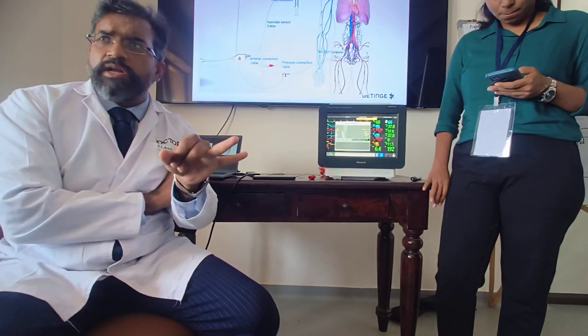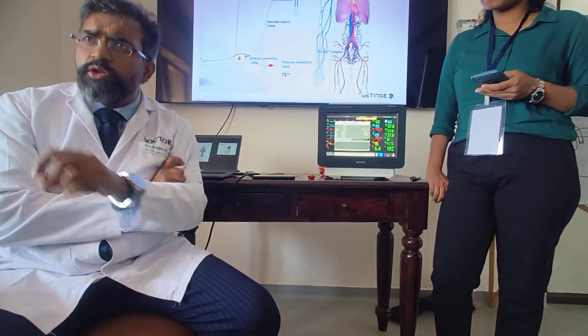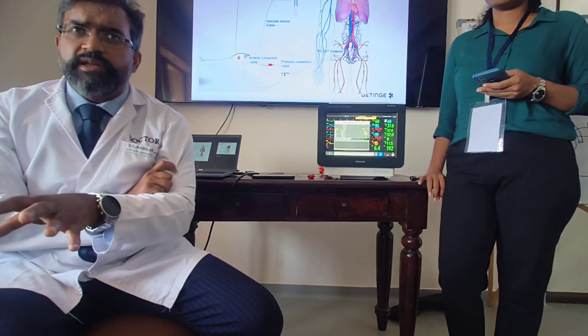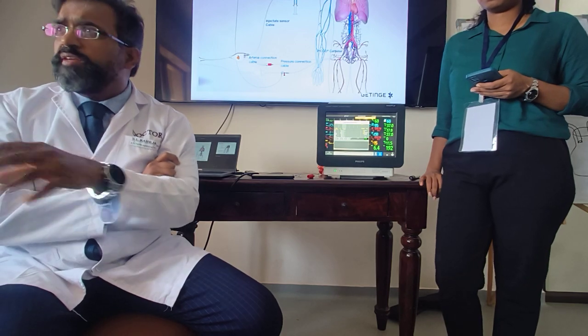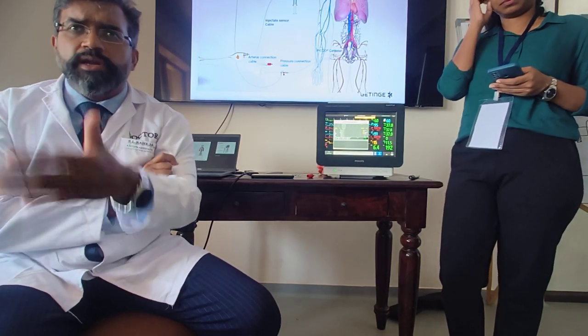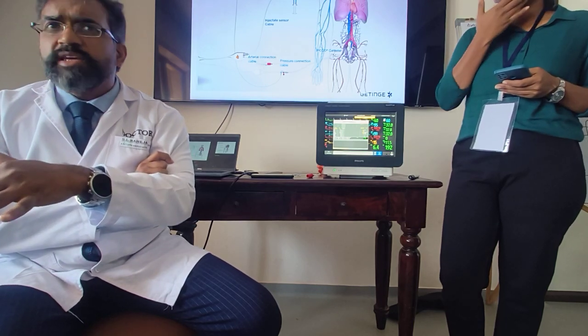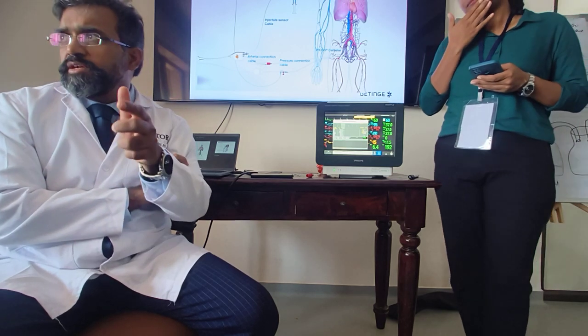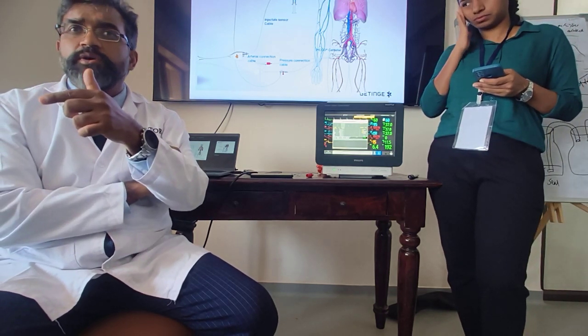The second thing is, when you do a thermodilution, first zero all the lines. Zero the lines first. Zero all the lines that are there, properly. Anyway, every 8 hours you have to zero the lines, so that protocol has to be in place anyway. The third thing you do is flush the lines. You flush the lines. Then you go ahead and do a thermodilution.